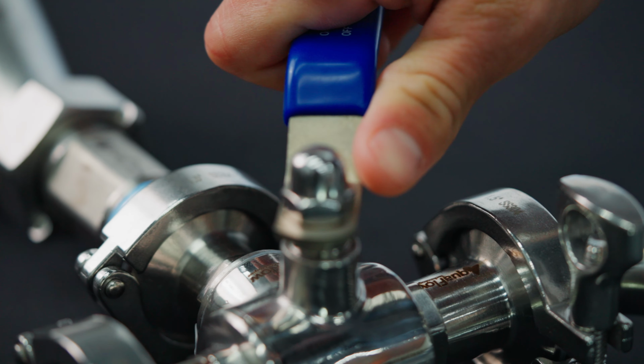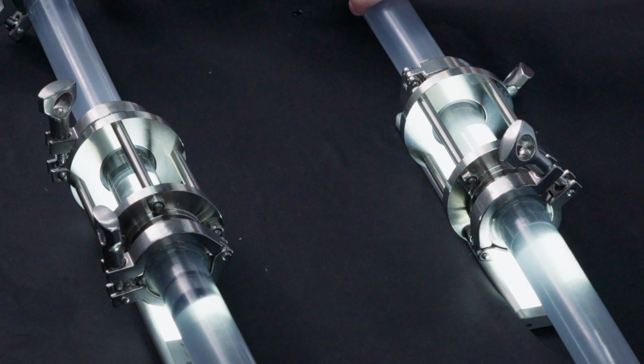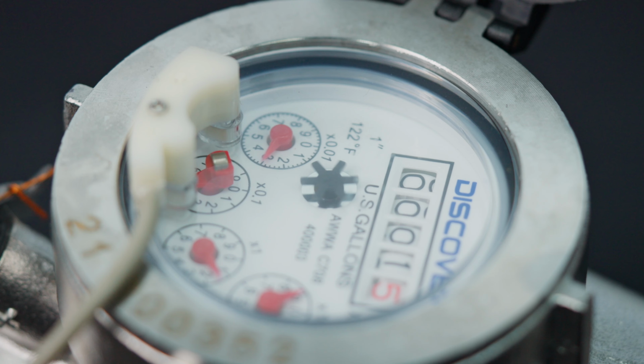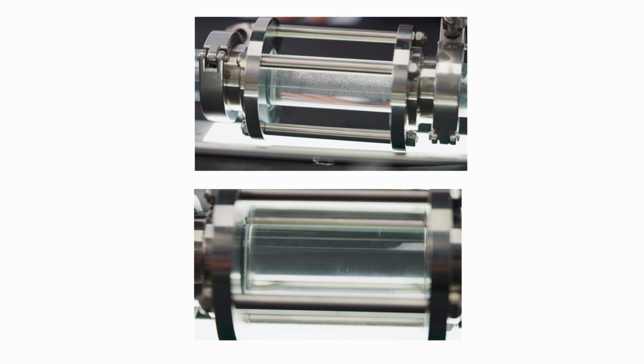Now here I'm going to change the flow to the FCD and watch how the flow acclimates from turbulent to laminar flow. The compression zone created by the FCD in a laminar flow will continue upflow through the meter, reducing the meter registering less gallons for the same amount of water delivered. Now when we turn the flow back to the line without the FCD, the water flow assumes its previous turbulent flow, and the air bubbles that were displaced in the water are now visible again.